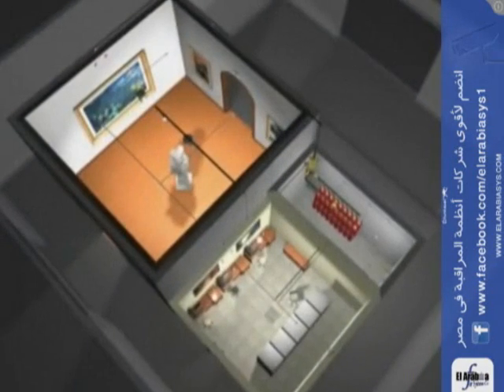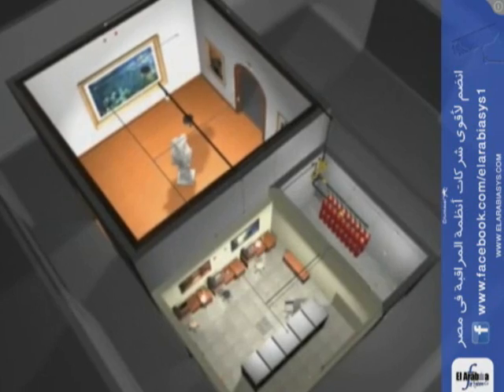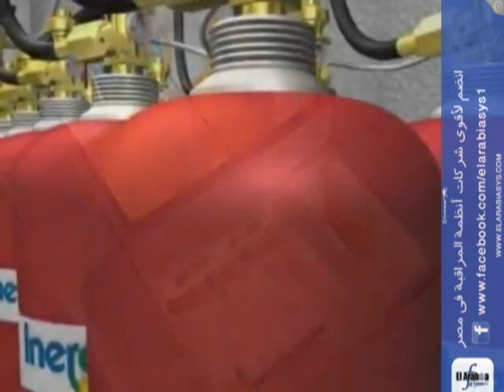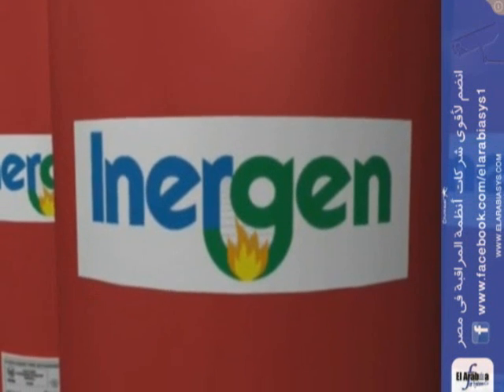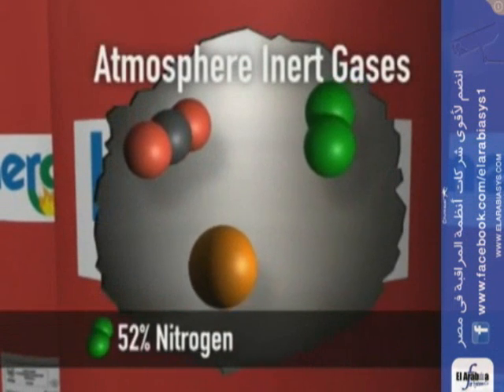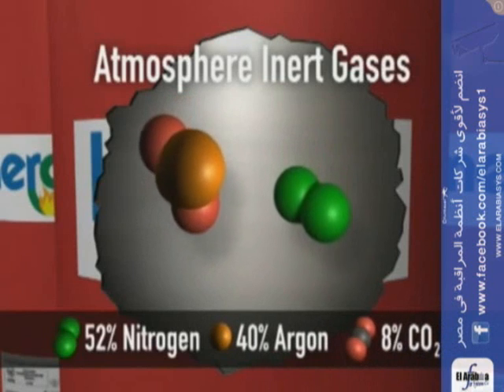An Inergen clean agent fire suppression system is both innovative and flexible in design. Inergen is a combination of three naturally occurring inert gases from the Earth's atmosphere. It is comprised of 52% nitrogen, 40% argon, and 8% carbon dioxide.